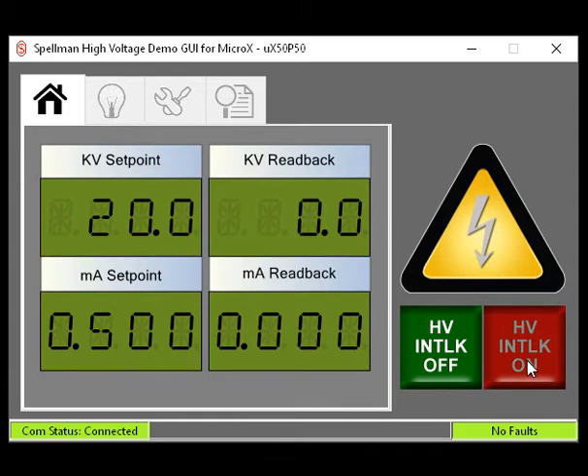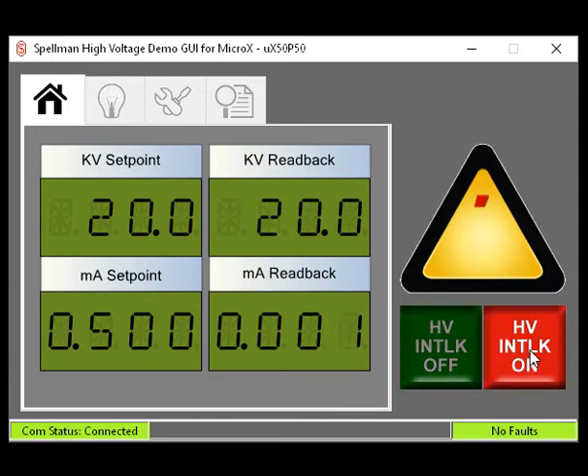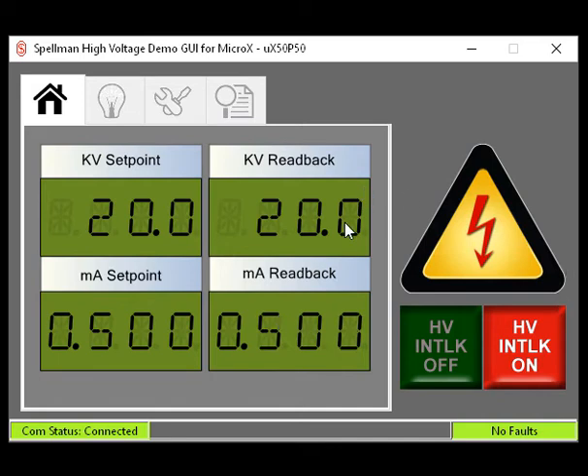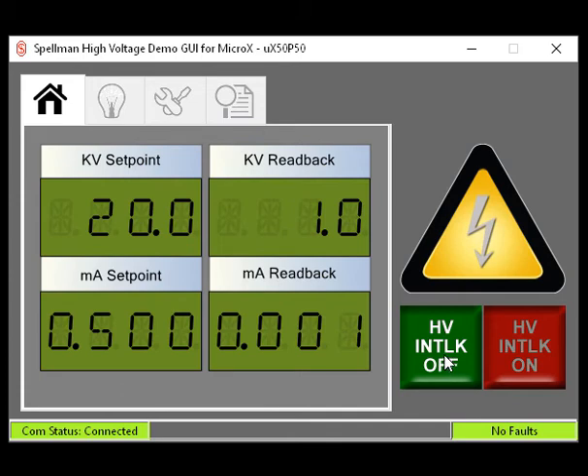Click the red High Voltage On button. You should hear a relay click. The red button will get brighter and the yellow high voltage warning symbol will display a high red warning arrowhead. Notice the KV and MA readback displays are showing the actual KV and MA being generated. You are now making X-rays. Click the green High Voltage Off button. You should hear a relay click and the generation of high voltage and X-rays will cease.